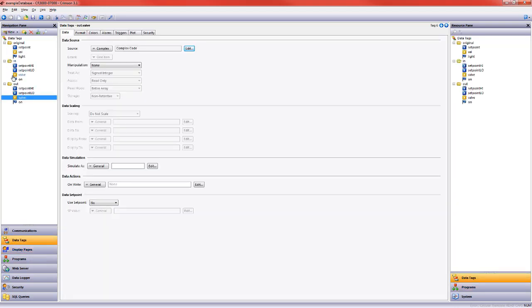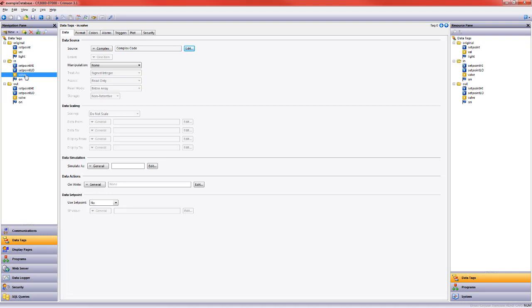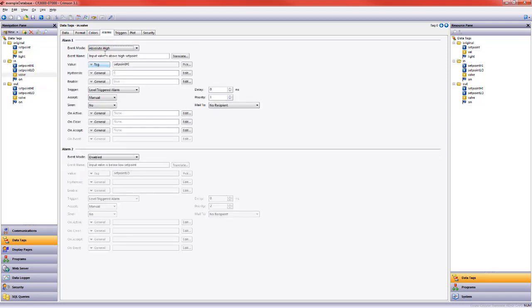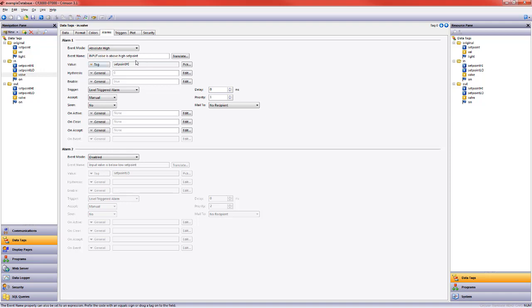Alright, now what I want to do is set some set points for the input and output valves. So I'm going to come here to my alarms tab in the editing pane. I'll go ahead and choose absolute high for this first one. You can see I've typed something in already. This one says input valve is above high set point. We then need to tell it what are we comparing the valve value to. In this case it's set point high which I just dragged over like that.